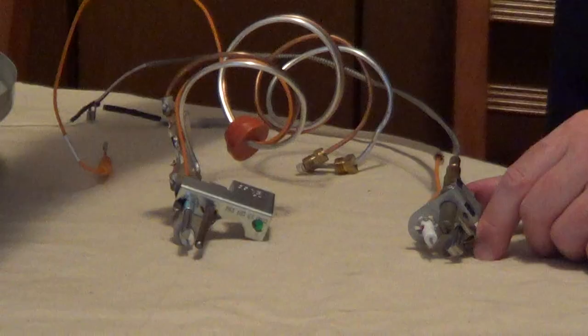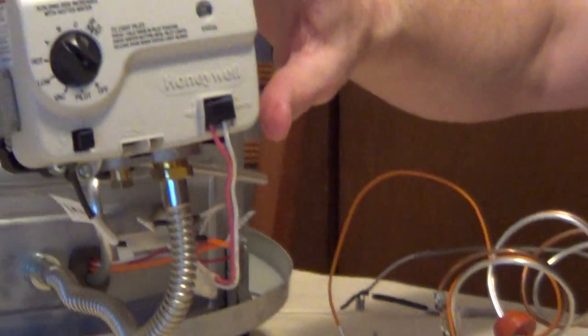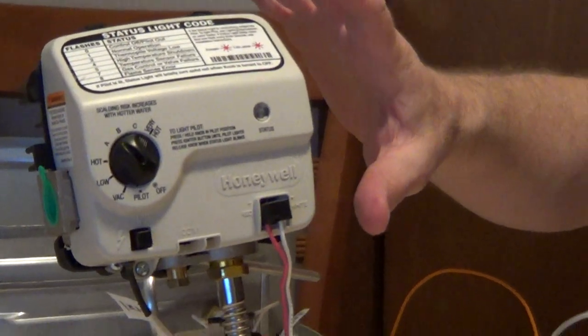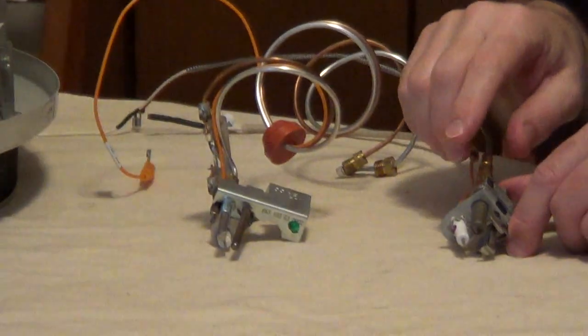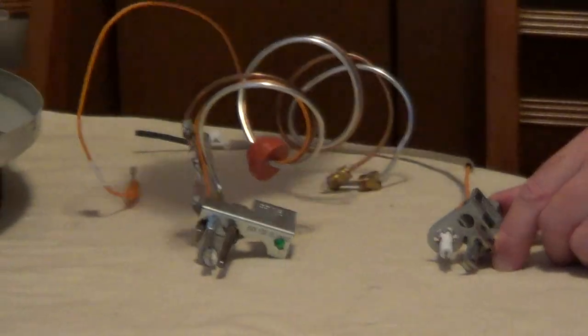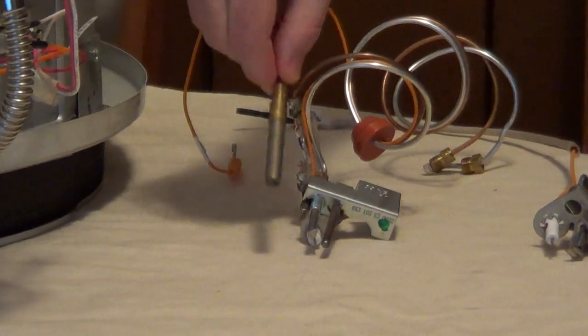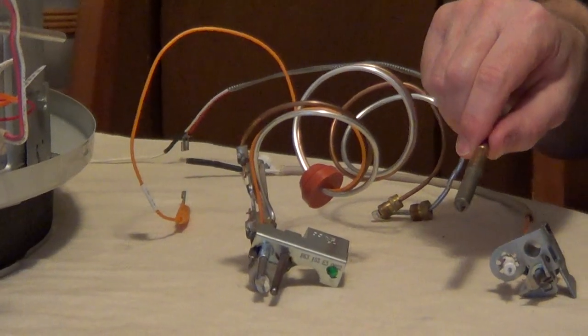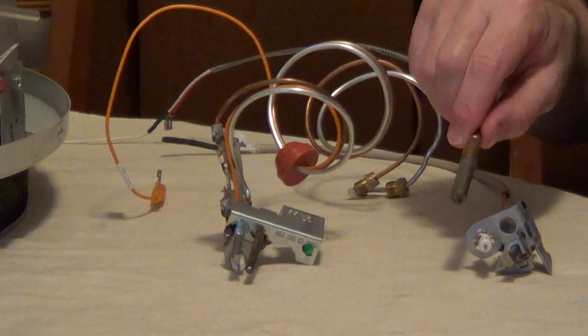Now, if you have any of the water heaters after 2010 that have an electronic gas control and it's self-diagnosing, they're going to be using a thermopile. You can see that this is much larger than the thermocouple, and this thermopile is going to generate about 750 millivolts.